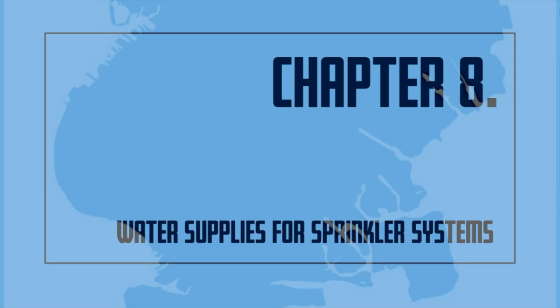A single water supply would appear to be all that is needed to supply a sprinkler fire protection system. This assumes that there is enough water at an acceptable pressure. However, a single supply may be out of service for maintenance or repair during a fire emergency, or it may be disabled during a fire or before the fire is fully extinguished. Additionally, the water supply may fall below normal pressure or volume during an emergency. These are just a few reasons why it is good to have a secondary water supply. In some cases, it is required by law to have a secondary water supply source.